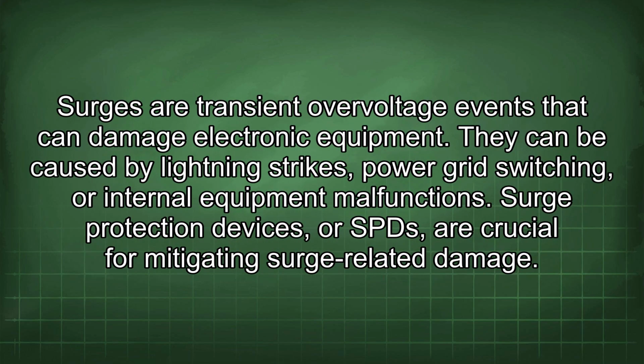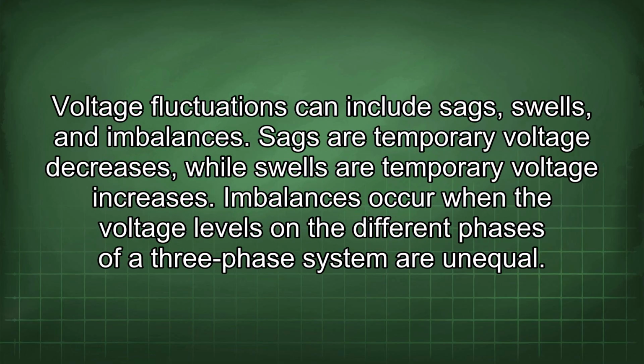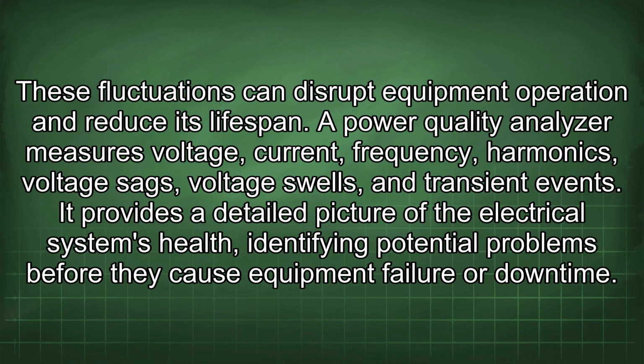Surges are transient overvoltage events that can damage electronic equipment. They can be caused by lightning strikes, power grid switching, or internal equipment malfunctions. Surge protection devices, or SPDs, are crucial for mitigating surge-related damage. Voltage fluctuations can include sags, swells, and imbalances. Sags are temporary voltage decreases, while swells are temporary voltage increases. Imbalances occur when the voltage levels in the different phases of a three-phase system are unequal. These fluctuations can disrupt equipment operation and reduce its lifespan.